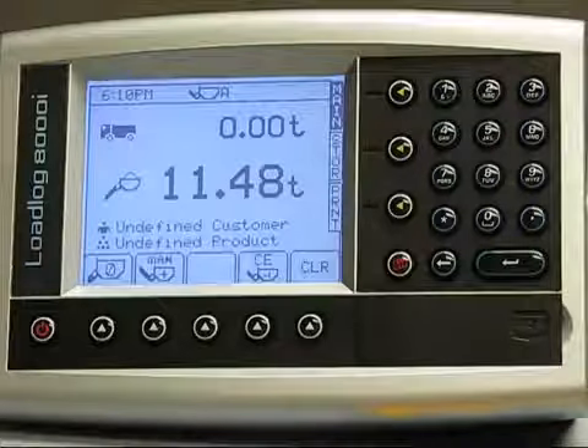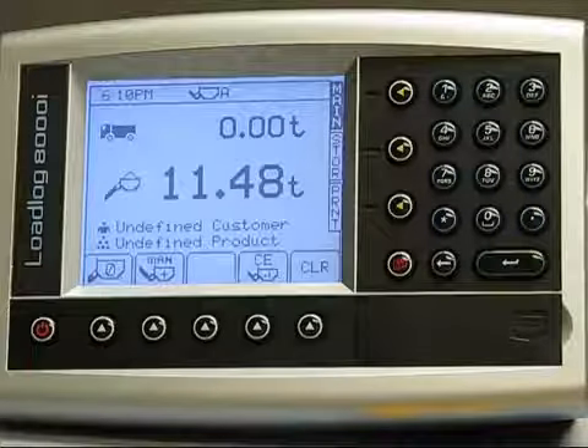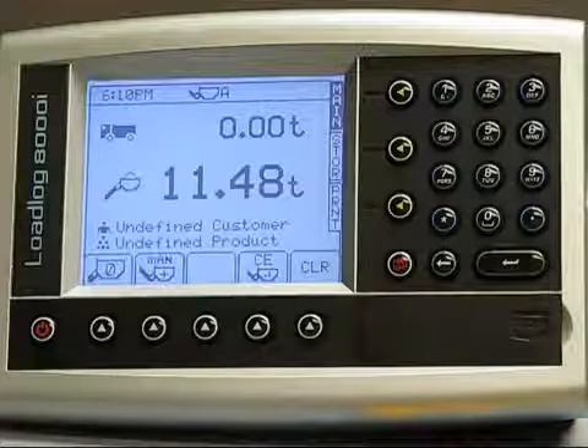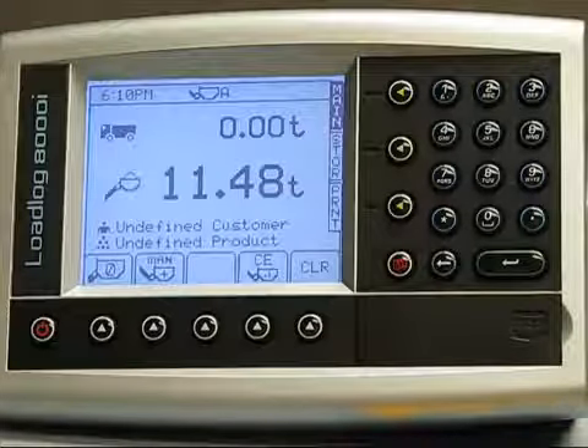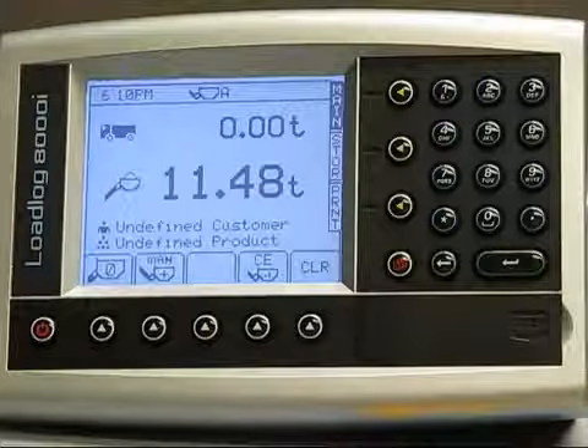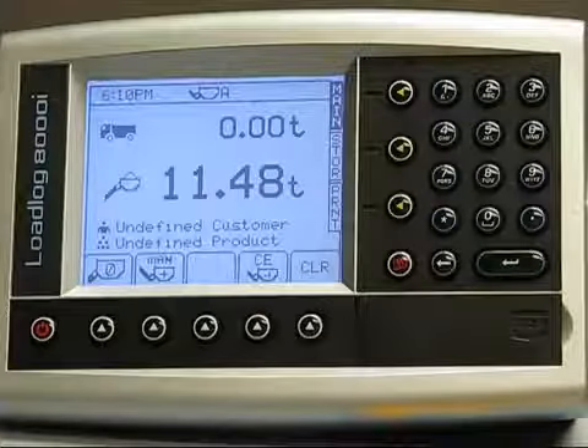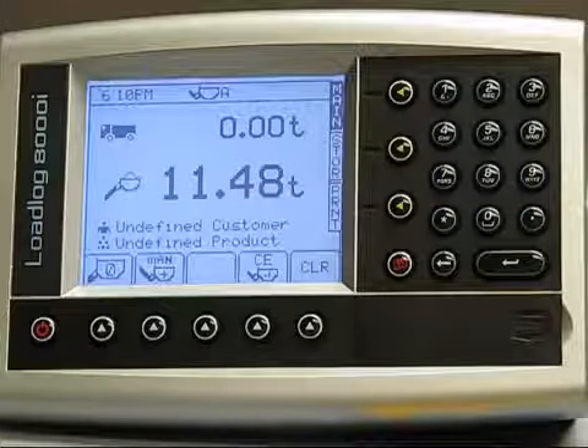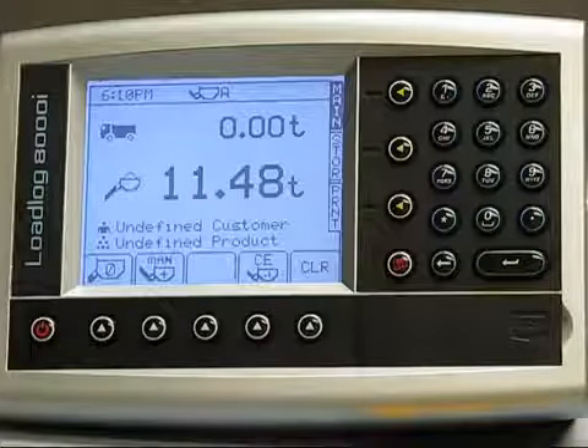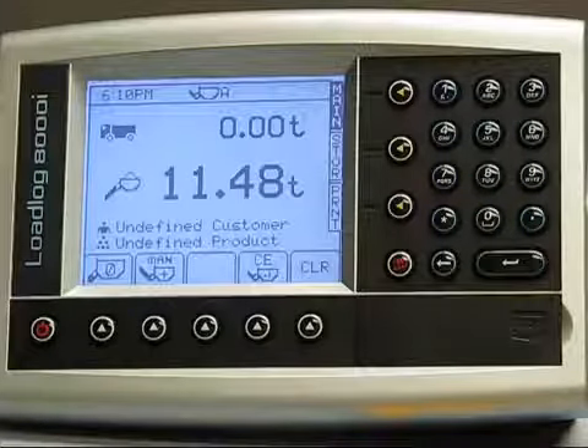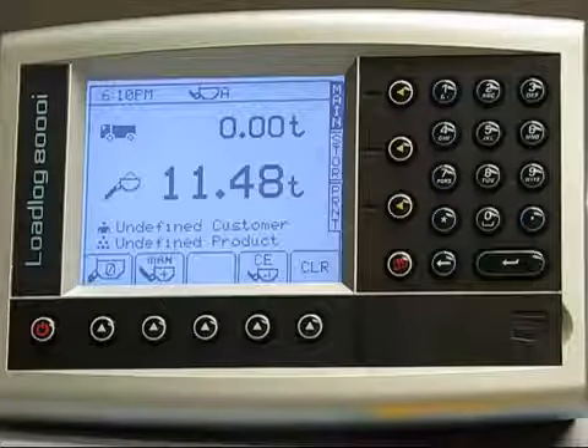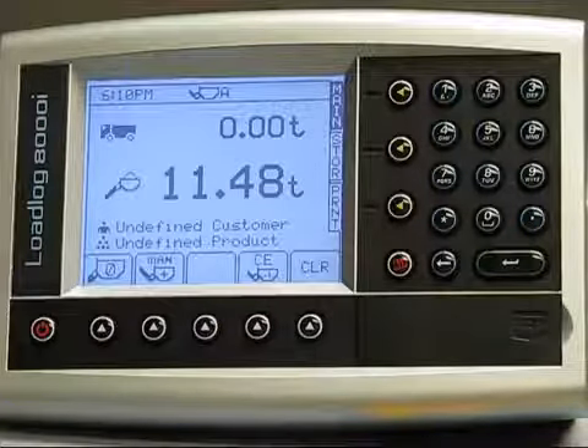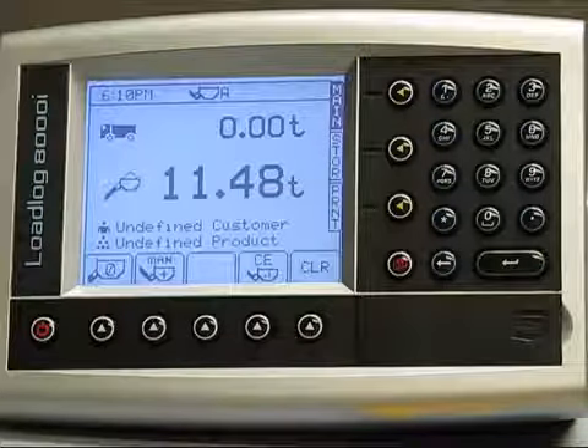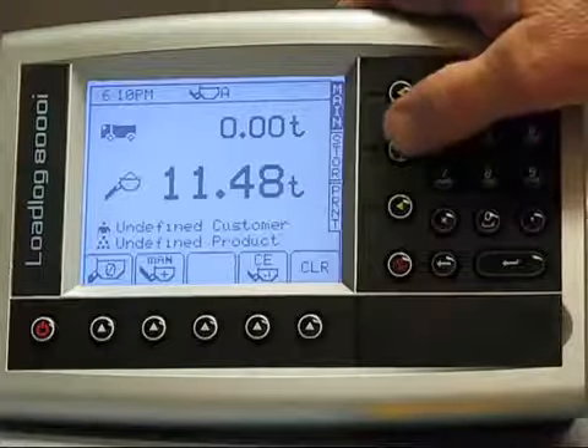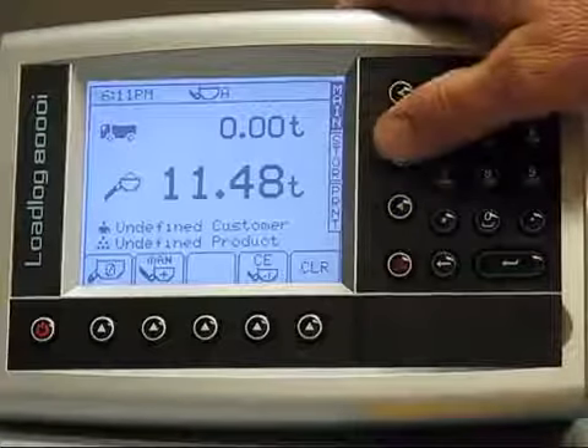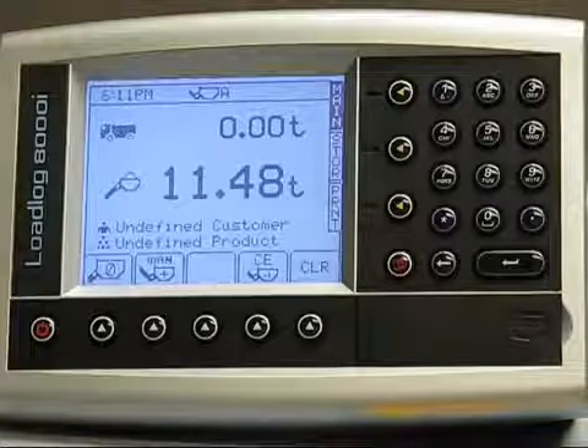When nudging based on a truckload, use caution because the truckload nudging is being done on multiple buckets, and remember that you are nudging the scale. Each bucket will go up by the percentage of the error. So if you nudge the scale by 5% based on 4 bucket loads, there is a possibility of nudging the scale too far in one direction. That should conclude the calibration and nudge portion of our discussion here for today.